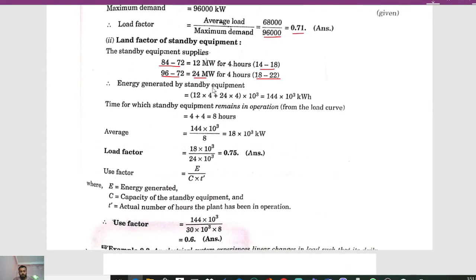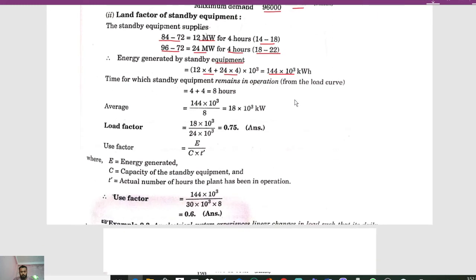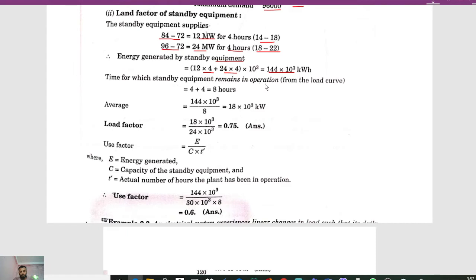Energy generated by the standby equipment is: 12 × 4 + 24 × 4 = 144 megawatt hours, or 144 × 10³ kilowatt hours. The time for which the standby equipment remains in operation is 4 + 4 = 8 hours. The average load of standby equipment is 144 × 10³ / 8 = 18 × 10³ kilowatt.